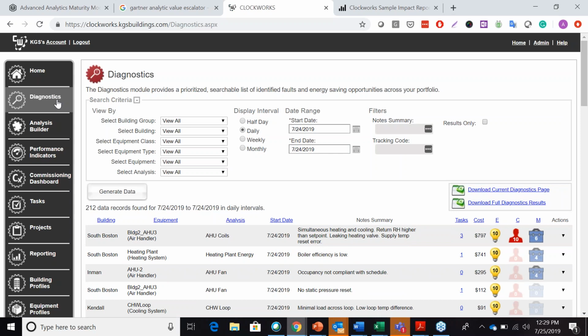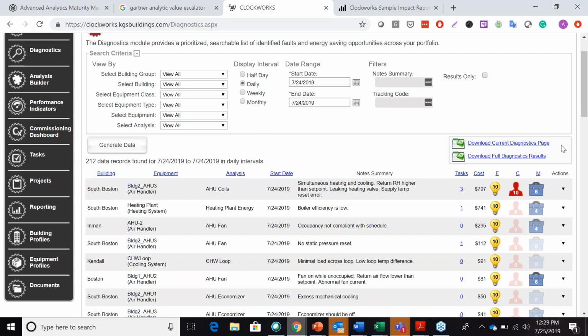So from an everyday perspective, most of our super users here, folks that are really in this tool on a daily basis or a weekly basis, depending on their workflow, they jump right into the diagnostic tool here. And this is that list. You could think about it as a punch list. It gets generated every single day that says, what are my top priorities? So right now we're looking at results from yesterday. 5-minute interval data, temperatures, pressures, flows, set points, modes of operation, all crunched down every single day to say, where are my priorities? I want to point out that it is a daily batch analytics run.